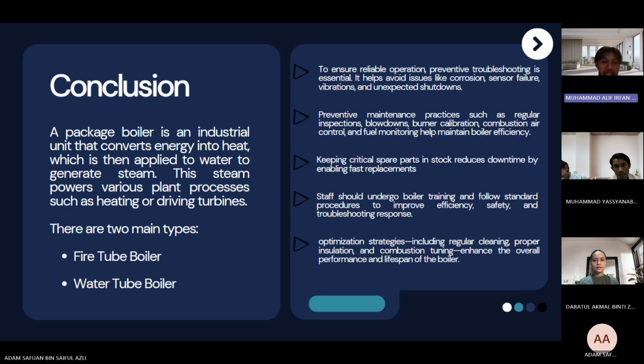In conclusion, a package boiler is an industrial unit that converts energy into heat, which is then applied to water to generate steam. This steam powers various plant processes such as heating or driving turbines. There are two main types, fire tube boiler and water tube boiler. To ensure reliable operation, preventive troubleshooting is essential because it helps avoid issues like corrosion, sensor failure, vibration, and unexpected shutdown. Preventive maintenance practices such as regular inspection, blowdowns, burner calibration, combustion air control, and fuel monitoring help maintain boiler efficiency. Keeping critical spare parts in stock can reduce downtime by enabling fast replacement.